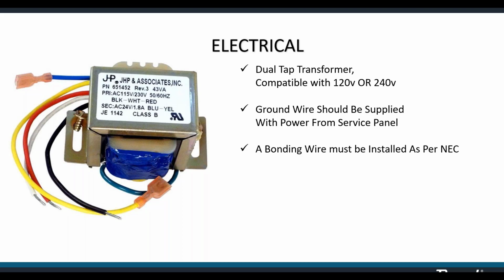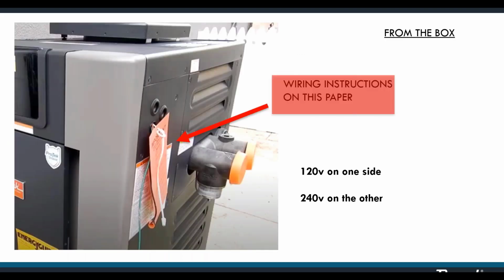There's no plugs, no wire harness, no clips, you know, 120, 240, white for this, red for that, black for this. None of that exists on this particular heater. Once you've wired it up, you're done. You're ready to go. Straight from the box, the transformer wires will be sticking out the side of the cabinet, and there'll be a red sheet of paper attached to that with wiring instructions on it.